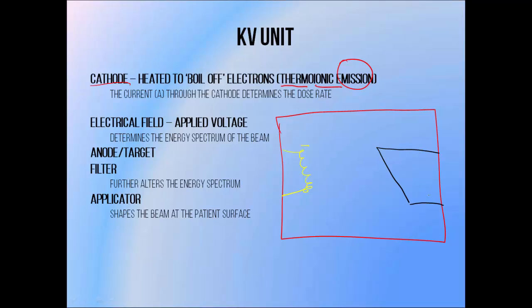On the other side of the tube we have the x-ray target, which we also call the anode, meaning something that electrons go to. In order to get the electrons from the cathode to the anode we apply a voltage, or electrical field. Basically we make the anode much more positive than the cathode in order to make electrons want to go there. The magnitude of the charge difference, or the voltage that we put between the two, determines how much energy the electrons get as they travel from the cathode to the target.